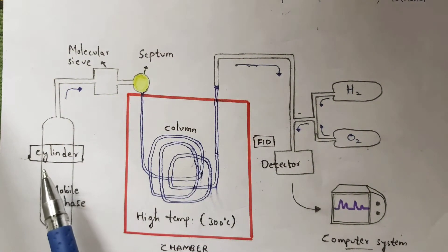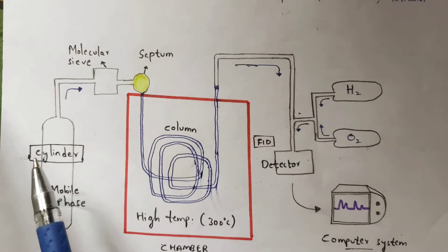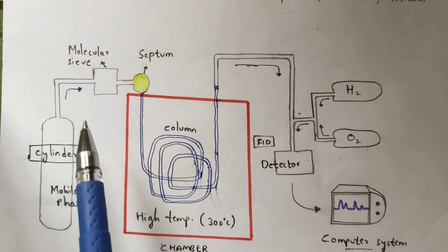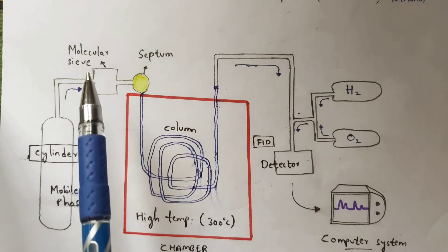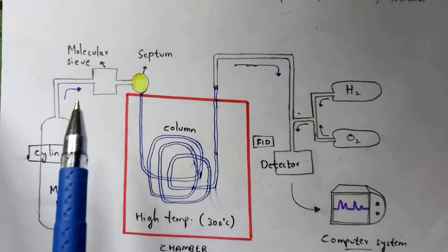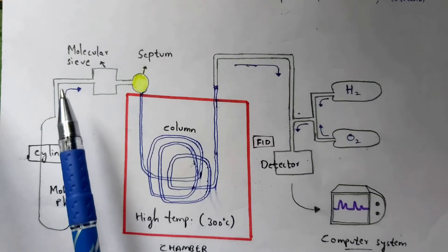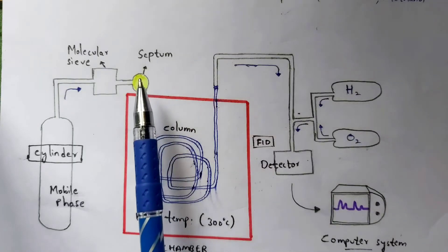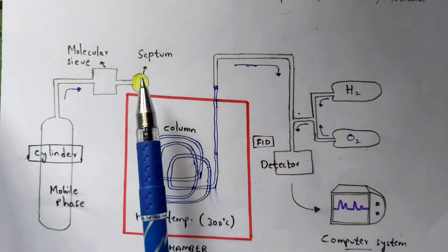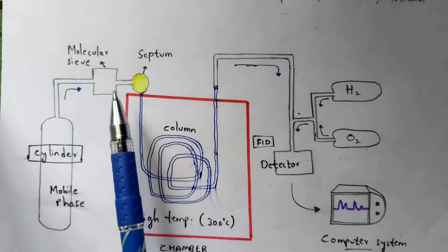Looking at the apparatus: firstly there is a cylinder containing the mobile phase gas, which is helium or nitrogen. Once this gas is passed on, it reaches the molecular sieve. The molecular sieve helps remove unwanted water vapor, hydrocarbons, and oxygen present in the gas. The gas then moves to the septum, where the sample is injected.